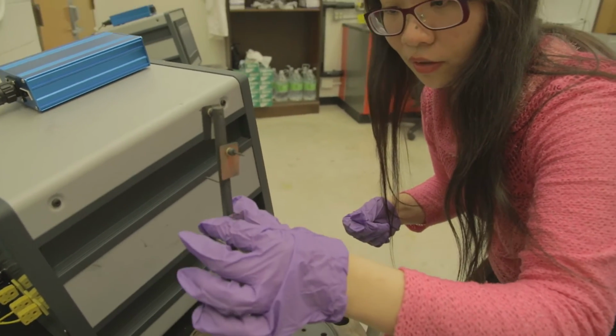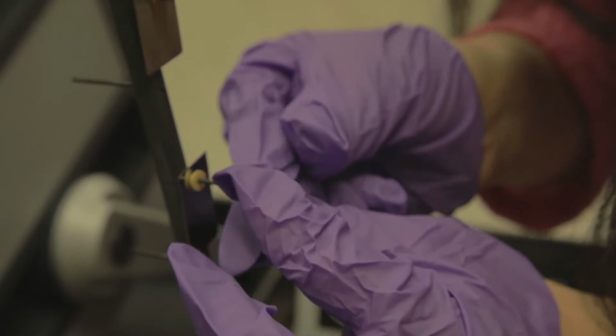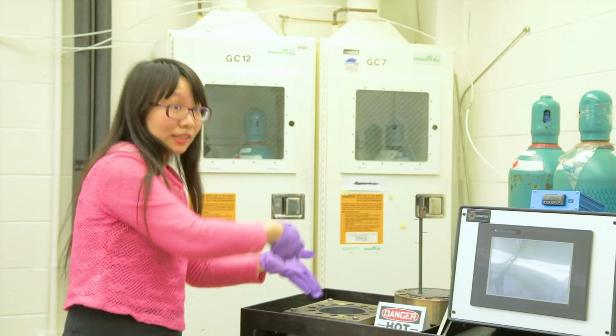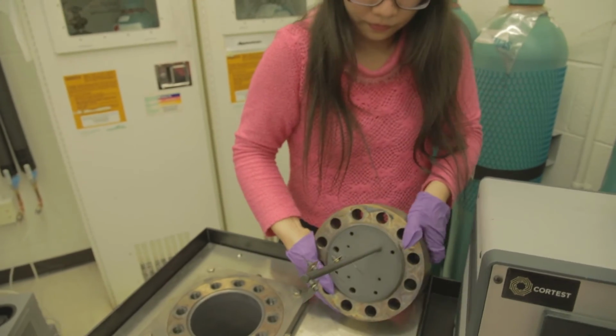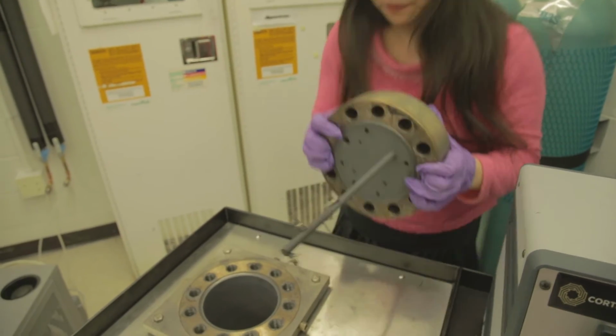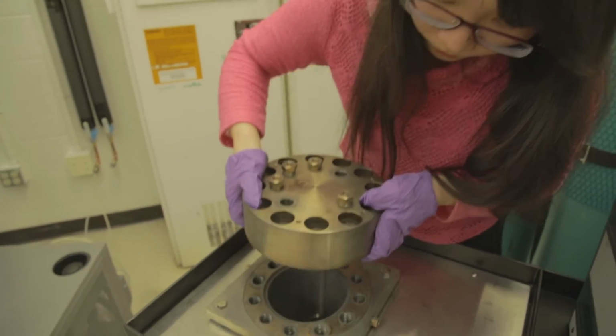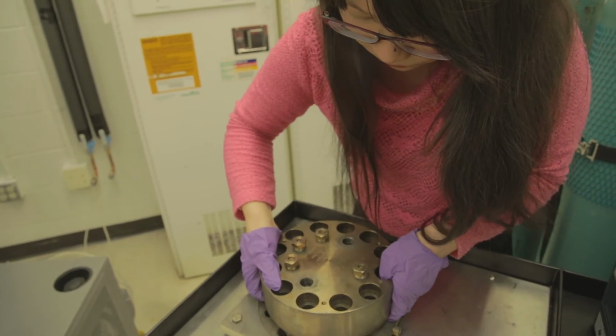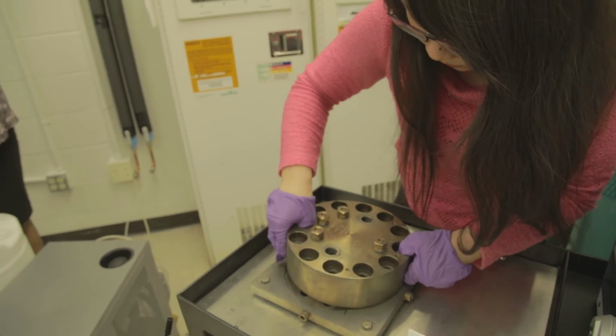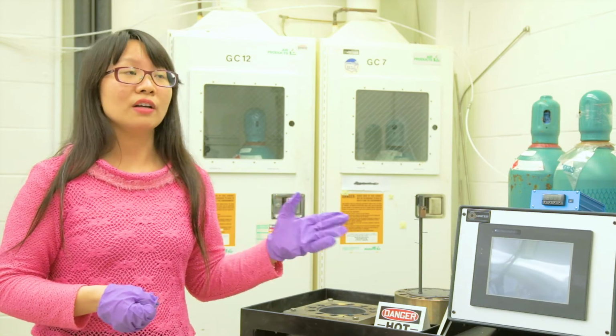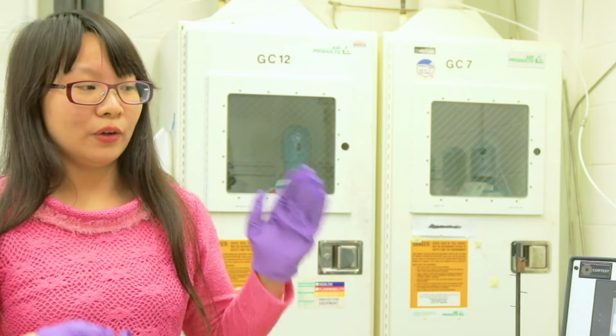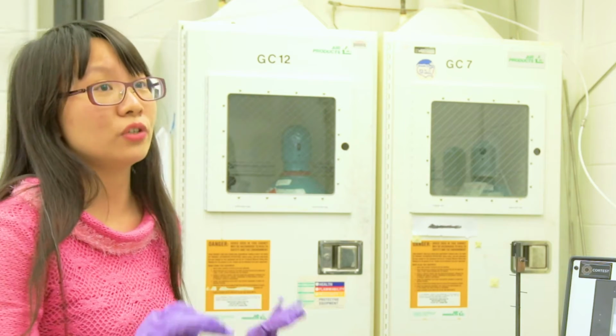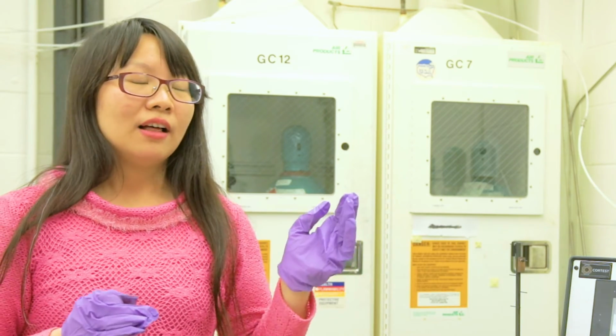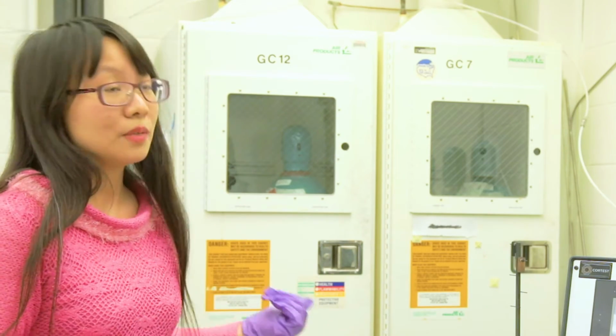This is one of the samples we have. As you can see, it's very shiny because we did some sample preparation and we put this sample on this tree. And we will flip this into the autoclave. And these two are static autoclaves. They are very similar to real reactors, but on a small scale. The temperature can go very high, around 325 degrees C, and the pressure is 2,500 psi. And there are two autoclaves because we want to separate different water chemistry solutions. One would be lithium hydroxide, and the other is potassium hydroxide.